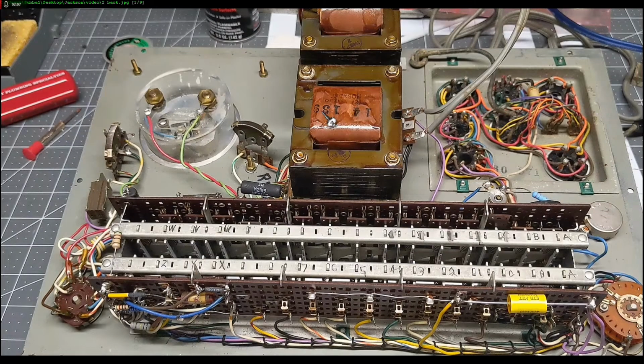Again, here's the inside. The switching is most intimidating because I don't know how the engineers ever figured this out for the thousands of types of vacuum tubes, to be able to switch in all the different elements for testing and switch in the different resistors required to load test that particular tube. But this R5 is the calibration test, the setup for the calibration of the plate, and this is your line control.